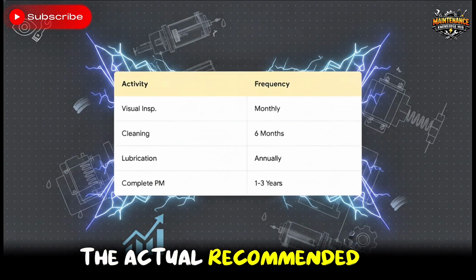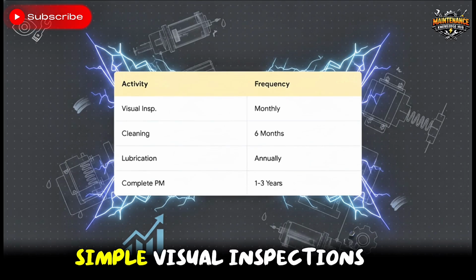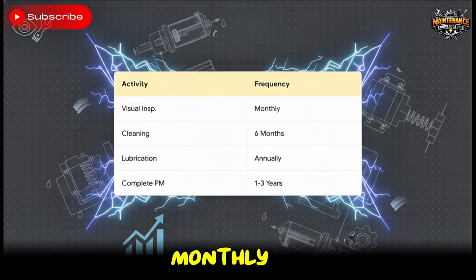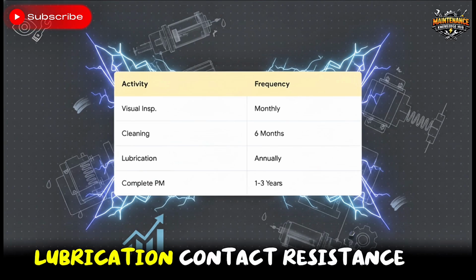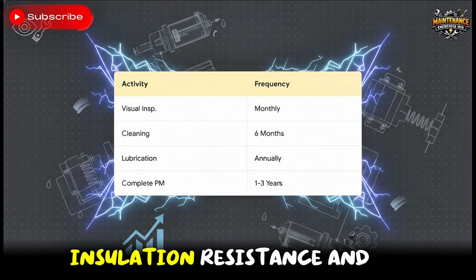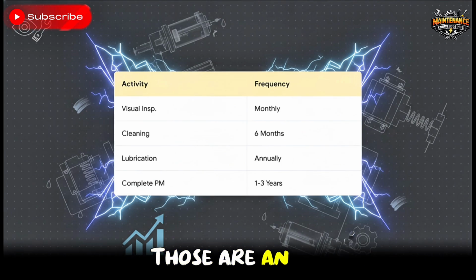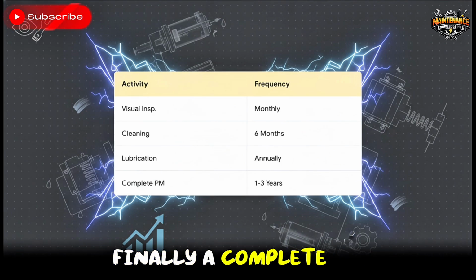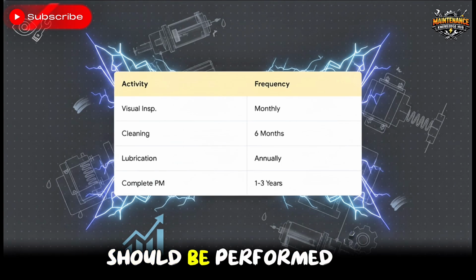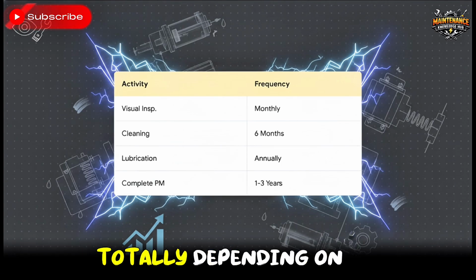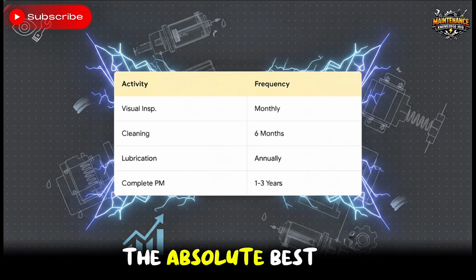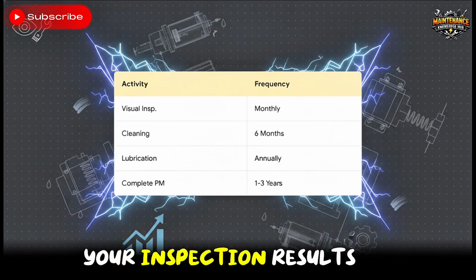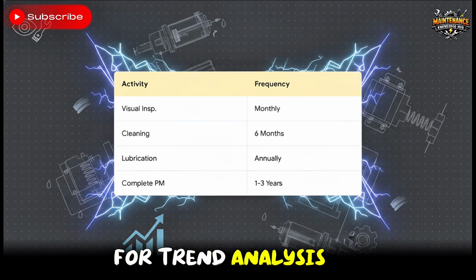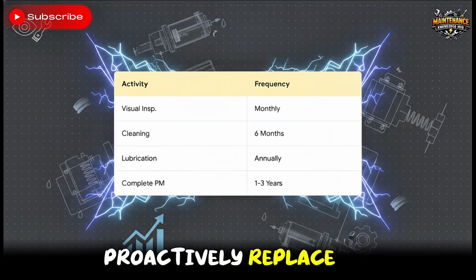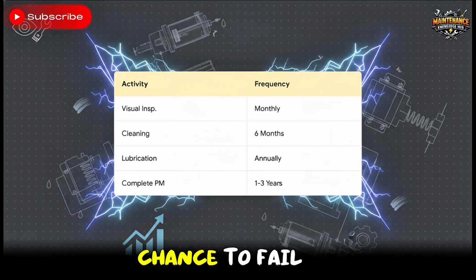So, what is the actual recommended frequency for all this work? Simple. Visual inspections should be done monthly. Cleaning and mechanical operation checks, put those on the calendar for every 6 months. Lubrication, contact resistance, insulation resistance, and timing tests, those are an annual activity. Finally, a complete top-to-bottom preventative maintenance cycle should be performed every 1 to 3 years, totally depending on your service conditions. The absolute best practice here is to record all of your inspection results and test values for trend analysis. Having that data allows you to proactively replace worn components long before they ever have a chance to fail.